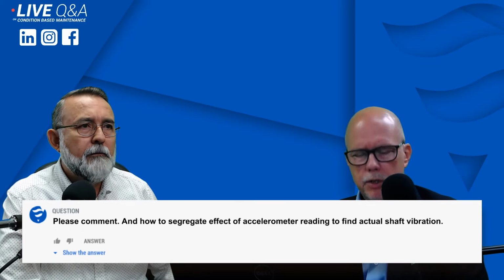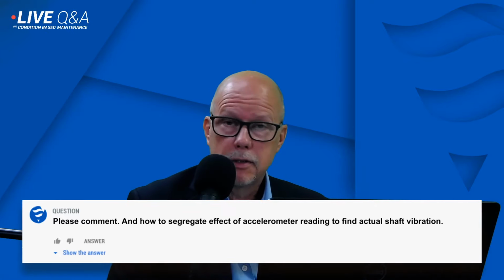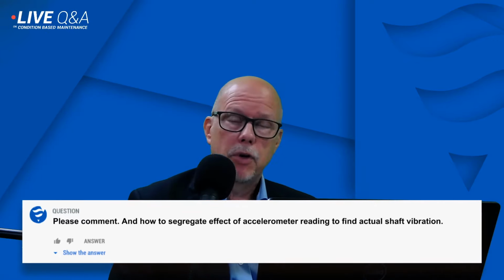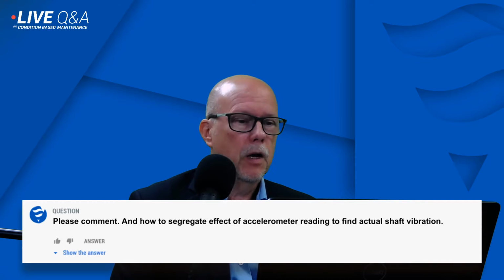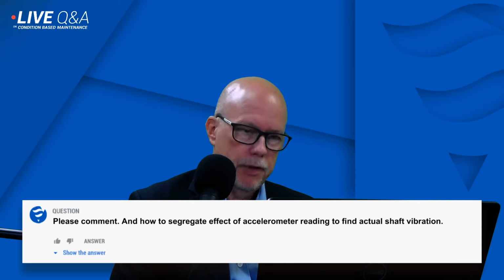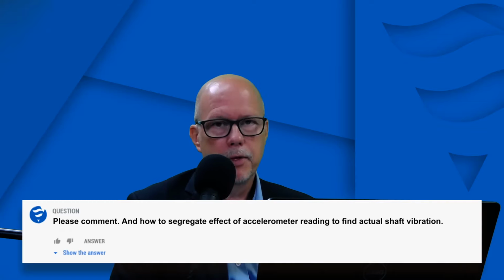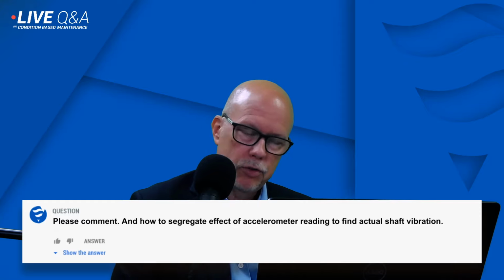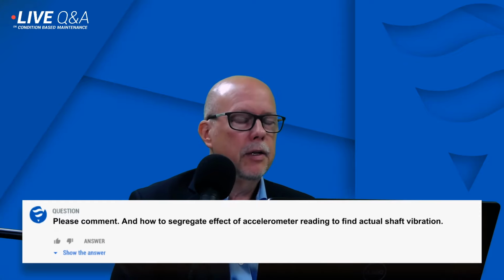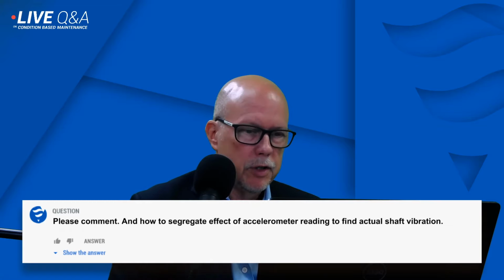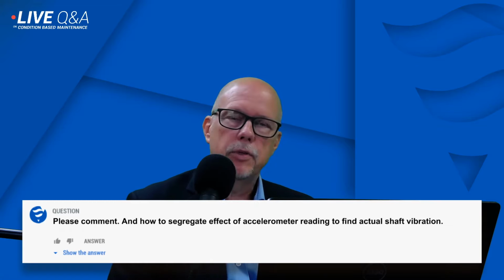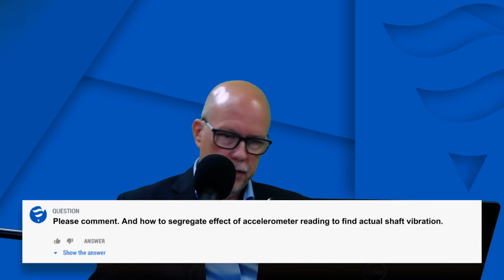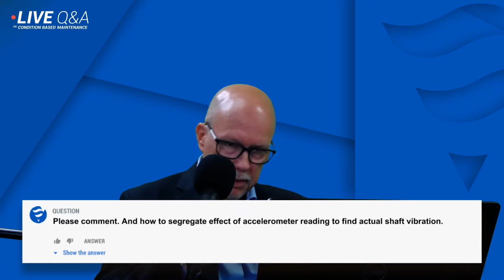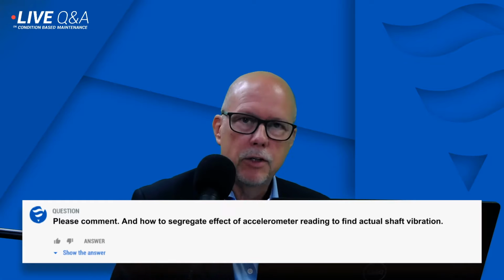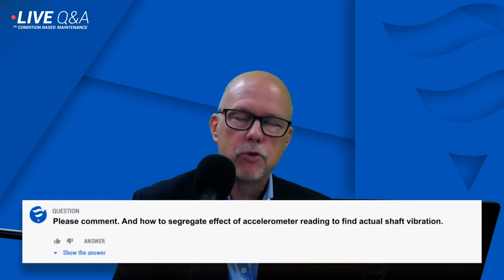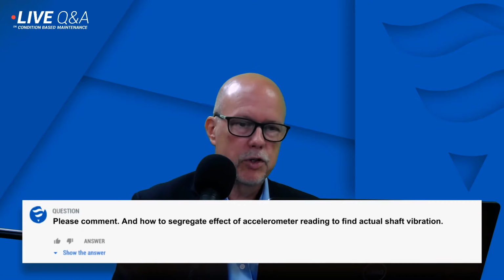Okay, what you do is of course, the accelerometers, well, in our case, the accelerometers are usually installed on the same bracket as the shaft displacement probe. So you're reading displacement off the shaft, and with the accelerometers, you will double integrate down into displacement. And of course, that creates a 180-degree shift, but you can adjust that. And then you can compare the results of both probes to see if they follow the same phase or not.